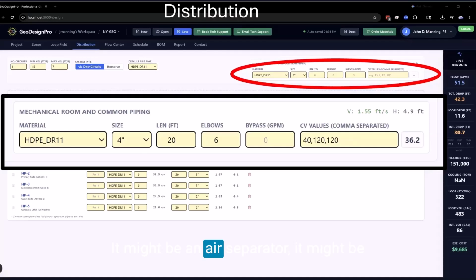It might be an air separator, it might be a triple duty valve, any number of things. You just put them all in a sequence separated by commas. It calculates the equivalent CV. It'll also tell you the velocity. With this low of velocity in the mechanical room, I might be tempted to drop it down to 3-inch. It'll give you the pressure drop. So just another facet of our tool.